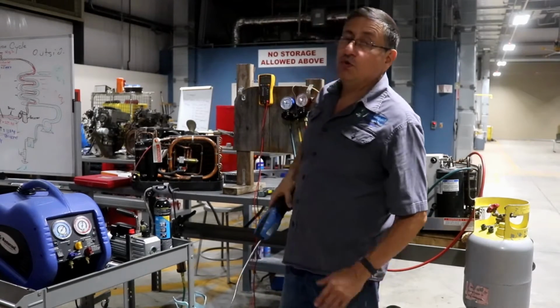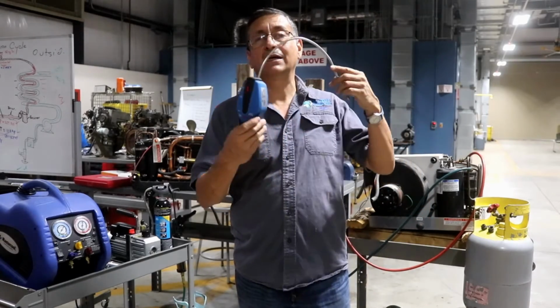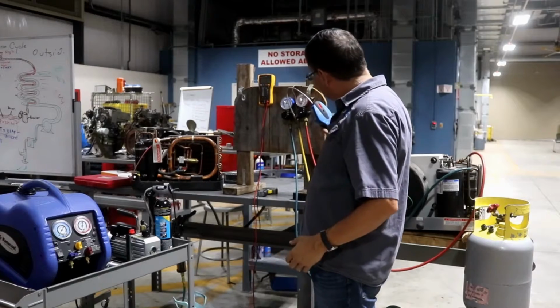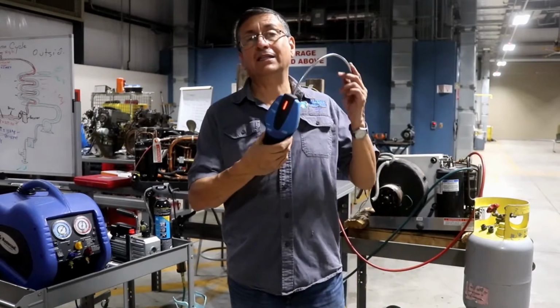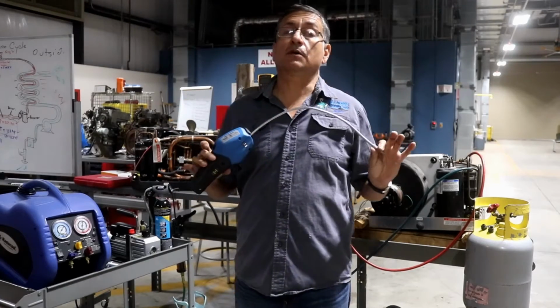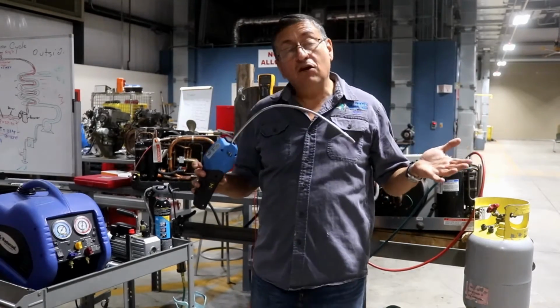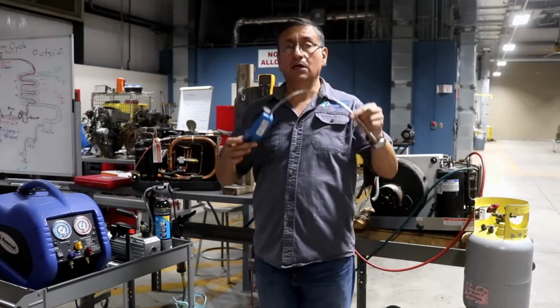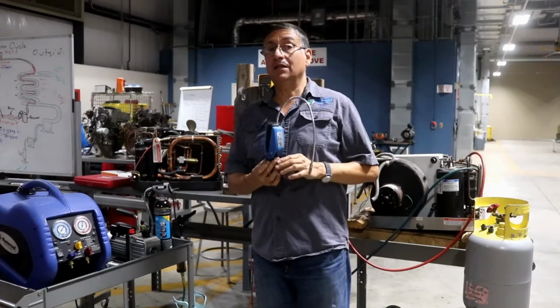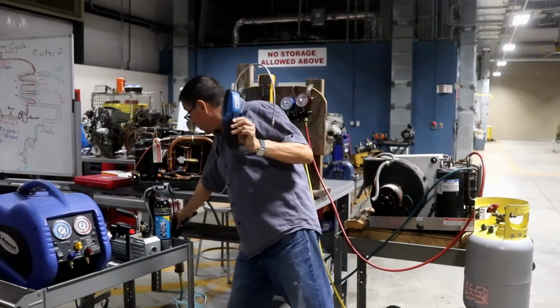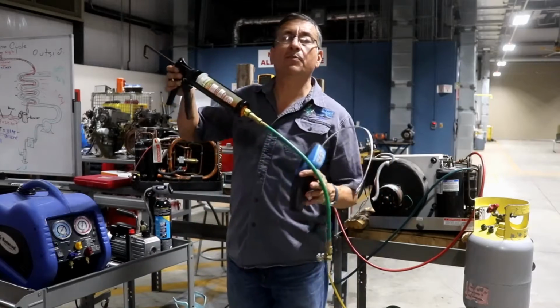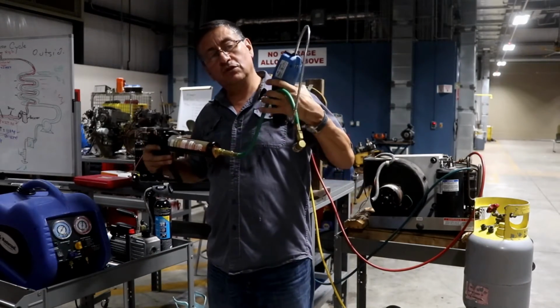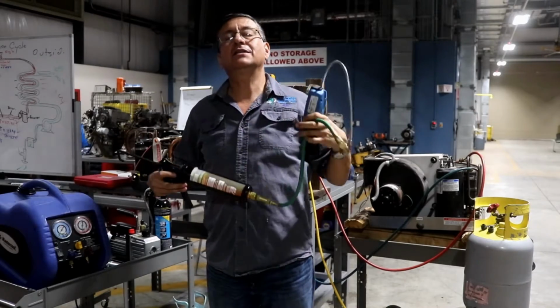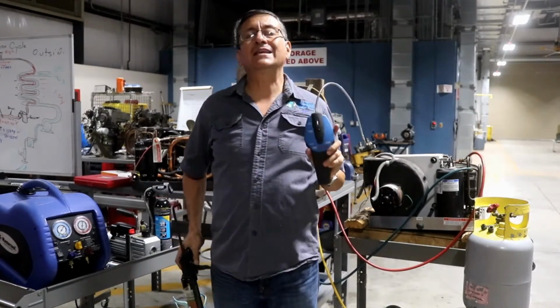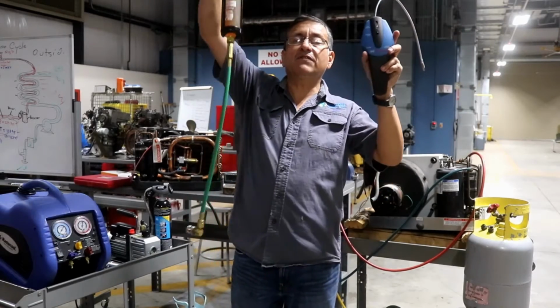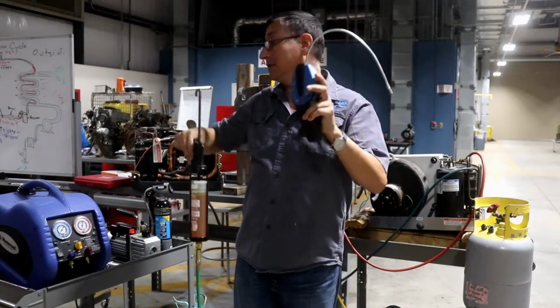We are going to verify the temperature all the time with this equipment, the temperature gauge. And also we are going to use this equipment. This is the leak detector. The leak detector is critical because in some cases you have a leak of refrigerant and you don't know where the leak is. With the leak detector, it's easy to identify. In order to use the leak detector, probably we are going to use this developer dye. We are going to introduce a little amount of this colorant in the system, and after that, with the detector, it's easy to identify where it is. We need both of them, the developer and the leak detector.